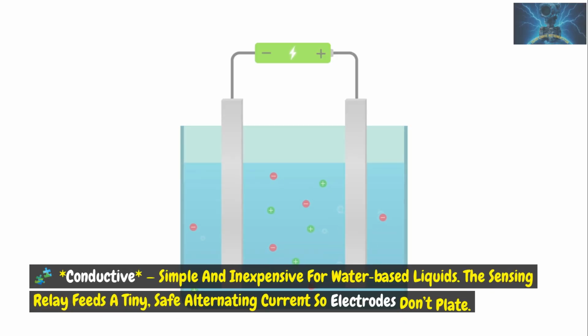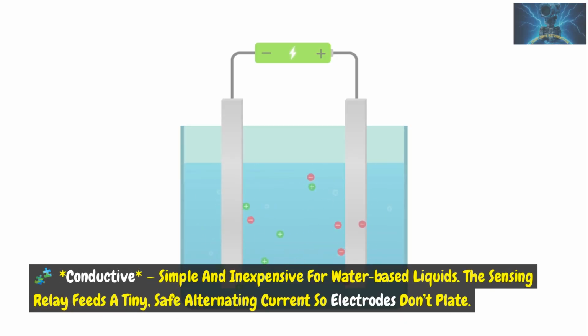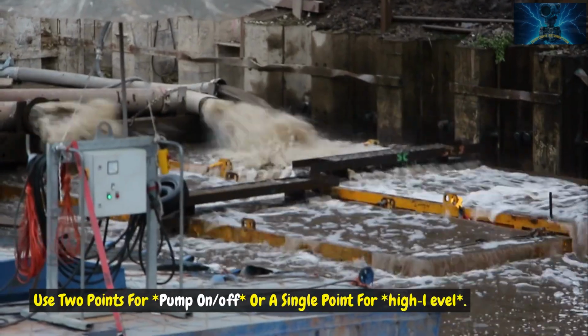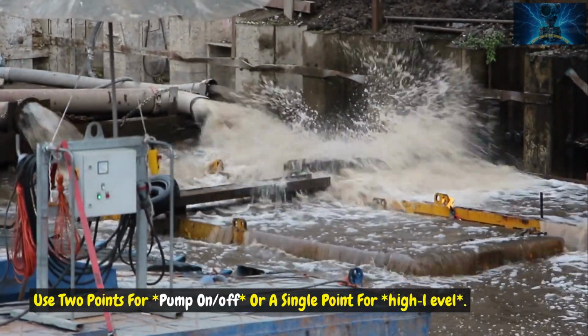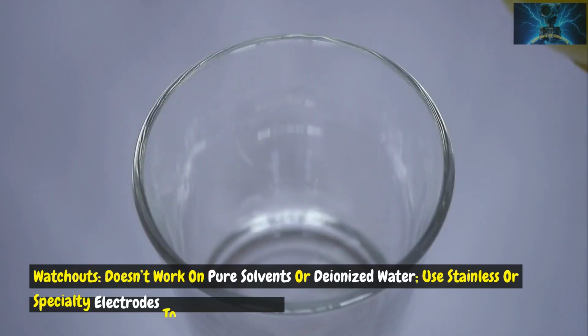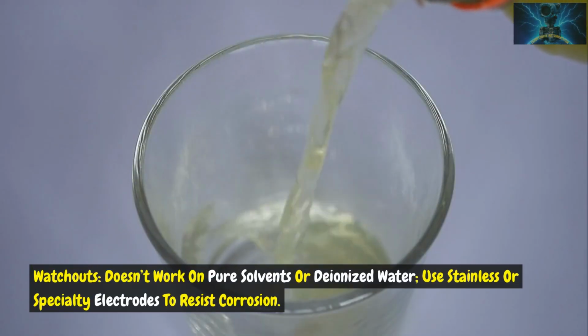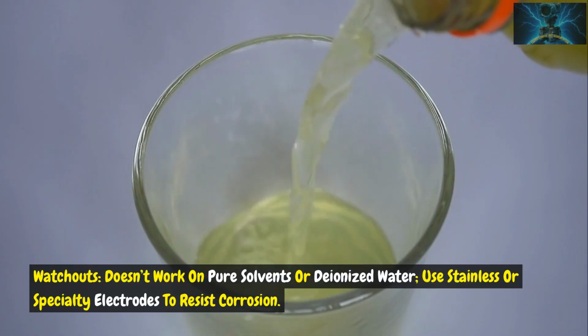Conductive: simple and inexpensive for water-based liquids. The sensing relay feeds a tiny, safe alternating current so electrodes don't plate. Use 2 points for pump on-off or a single point for high level. Watchouts: doesn't work on pure solvents or deionized water. Use stainless or specialty electrodes to resist corrosion.